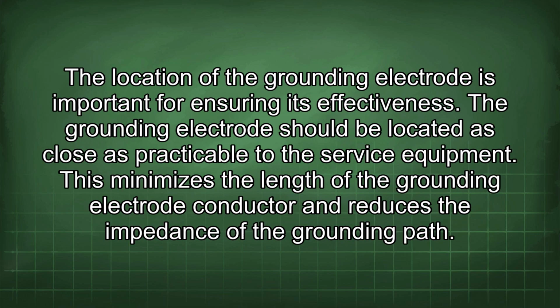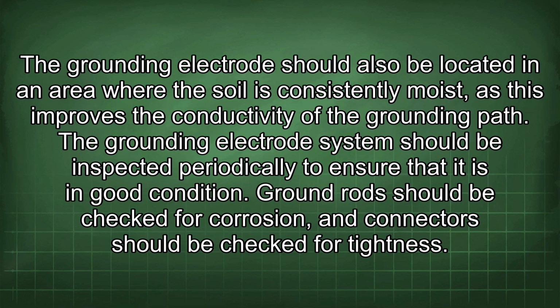The location of the grounding electrode is important for ensuring its effectiveness. The grounding electrode should be located as close as practicable to the service equipment. This minimizes the length of the grounding electrode conductor and reduces the impedance of the grounding path. The grounding electrode should also be located in an area where the soil is consistently moist, as this improves the conductivity of the grounding path.